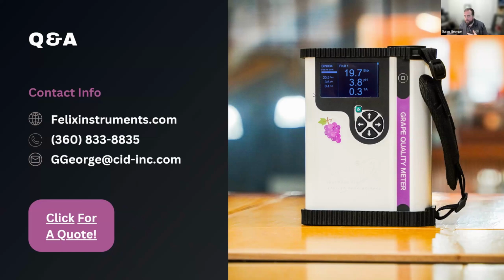Other than that, we have a built-in reference shutter that accounts for all your different lighting conditions, so you won't have differences when using it inside or outside. There's always a reference measurement taken with every single measurement, and there are no other major components that require maintenance. It uses rechargeable lithium-ion batteries, so you don't have to worry about the internal battery going bad. It's a very easy to use and low maintenance instrument. If something needs attention from us, the device comes with a standard 1-year warranty, and you can send it back to us for repair if it's a manufacturing defect of some kind, but that's a very rare occasion.